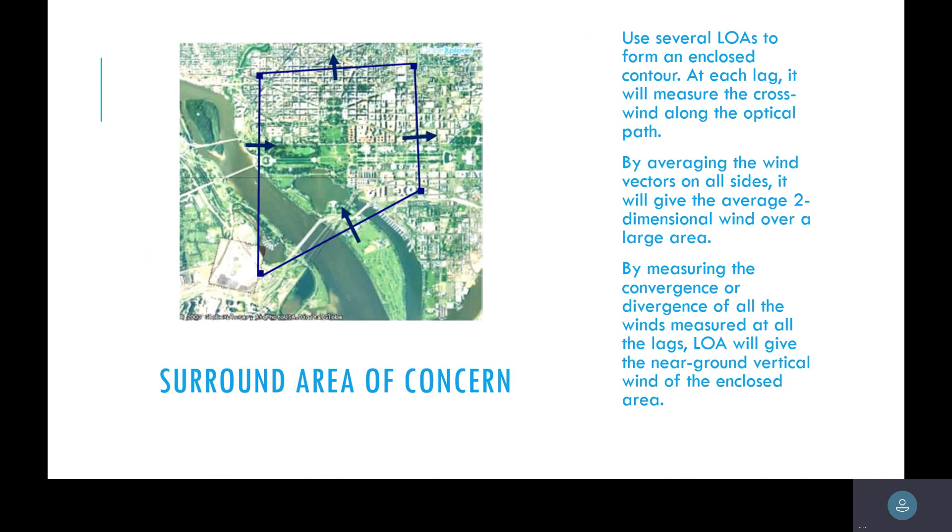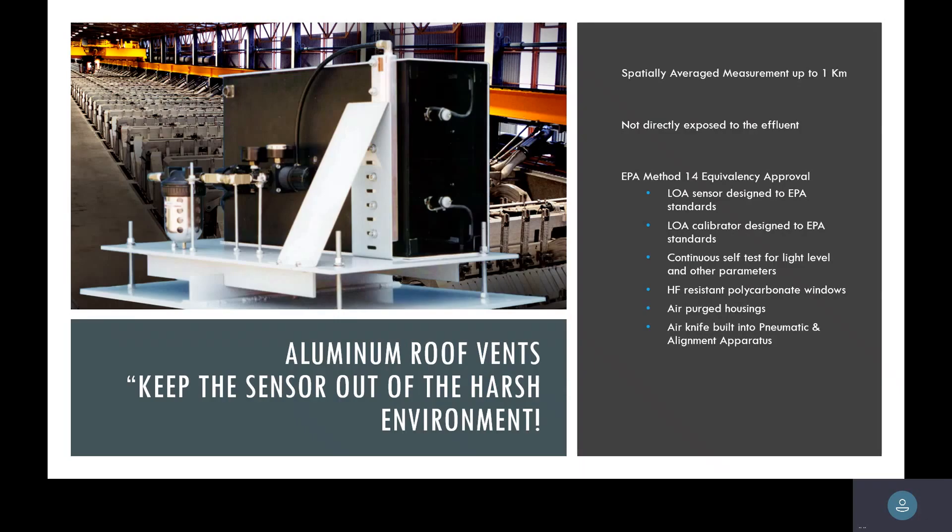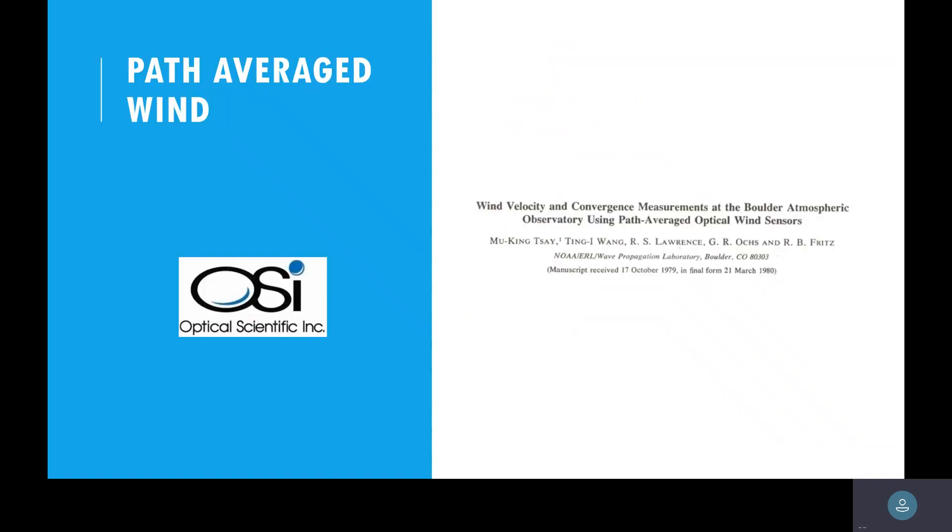Some of the applications that LOAs are used in: This is one where we shoot LOA across the pot rooms of aluminum smelters. Basically what happened was they were using anemometers and the HF was just burning those out every six months. So we put an LOA in there. The aluminum industry came to EPA and said, hey, we want to use this technology. If you guys want to use any technology, whether it's ours or anyone else's, you just go to EPA and say we want to use this because we think it'll help us.